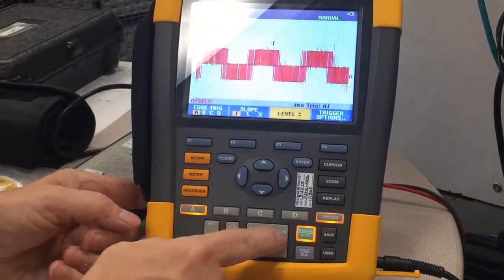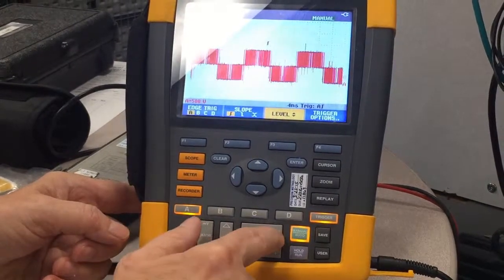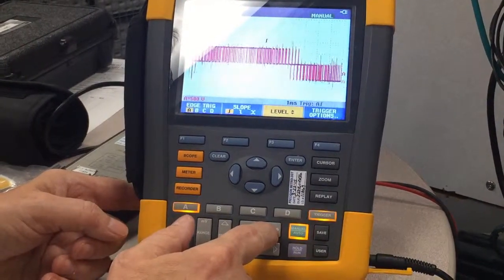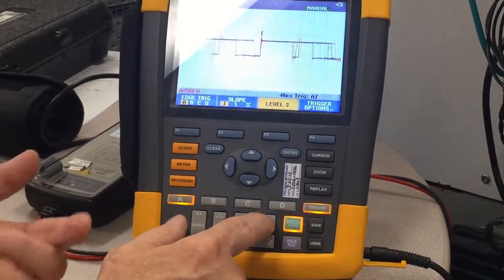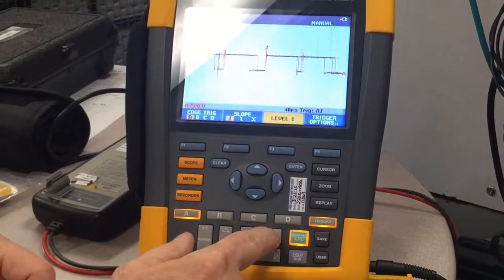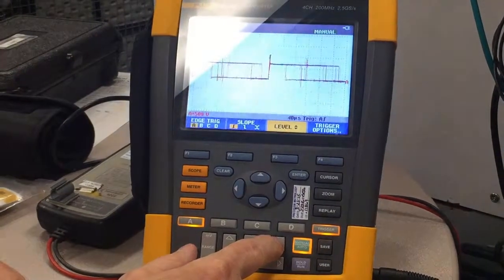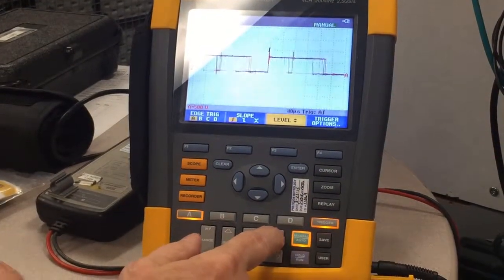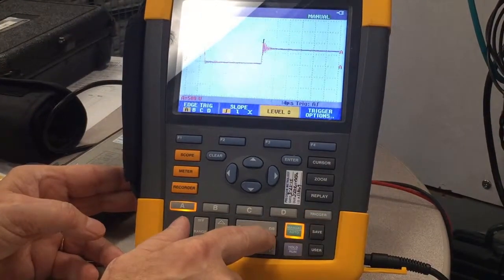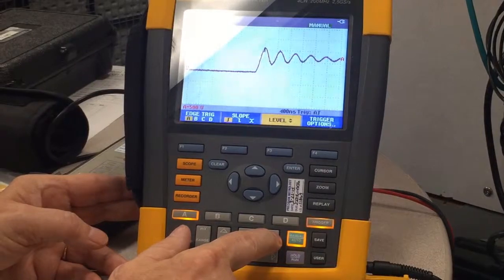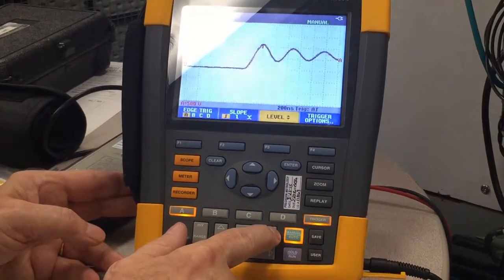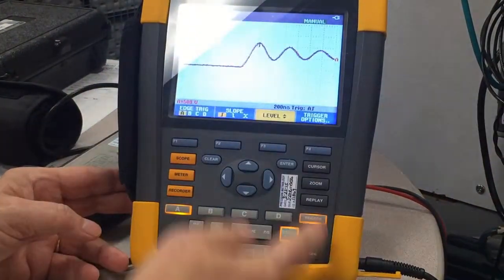And then, the next thing we want to do is we want to expand this waveform out. So, we take the time button and then press the NS side. So, we decrease our times per division. The whole goal of capturing a reflective wave voltage is to see the rise time of the voltage and the peak value. So, we keep on decreasing our horizontal scaling until we get a pulse, which gives us the rise time and the peak value.